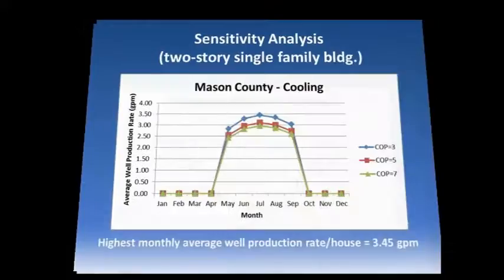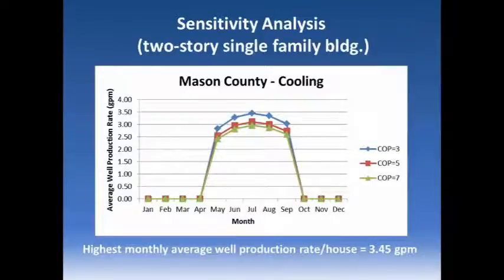There is a similar trend for the American Bottoms heating here. You can see that the highest still occurs in January, about 2.5 gallons per minute. For the cooling mode, it is different.